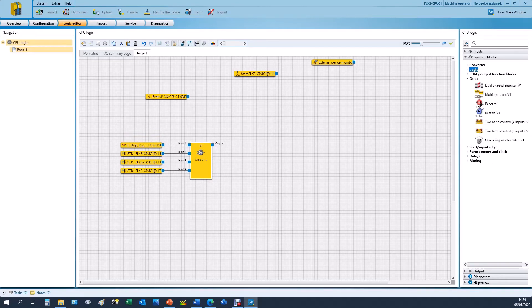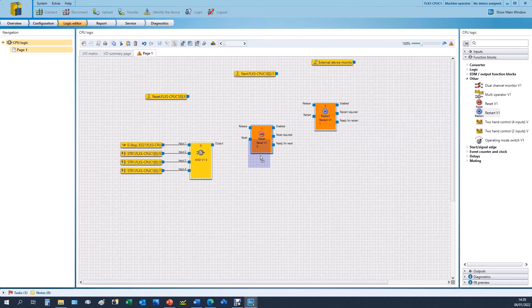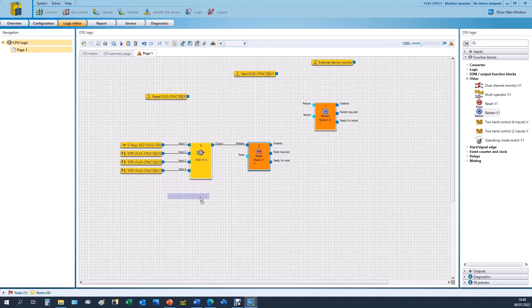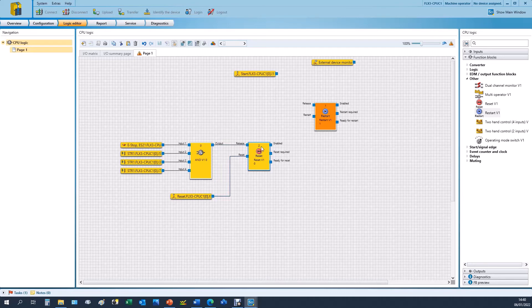Under other we also have our reset function block and our restart function block. So the release is when we're allowed to actually activate this reset block, and then all we need to do is wire up our reset input to the reset input and then we have a yellow block. So that when the release goes high you press the reset and then we can enable the output. We'd also like to have a reset required flashing signal on the button.